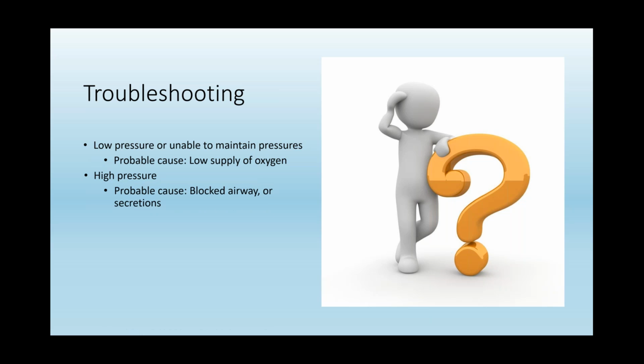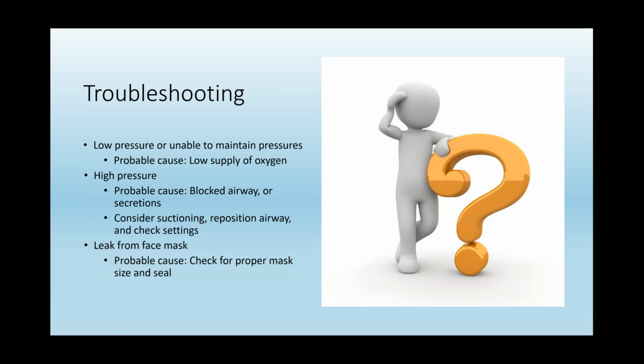If you have a high pressure, one of the probable causes is that the patient has a mass amount of secretions, or their airway is blocked for whatever reason. So you could try suctioning them or repositioning them. Like I said, in theory they're supposed to be sitting pretty high up in a seated position, so maybe reposition them. Check that the settings and the oxygen flow are appropriate. And then the leak issue, which I keep mentioning, seems to be the most common one for me at least: there's a leak in that mask. So check that you have a proper seal. Or maybe you're using a mask that's too small or too big, and you need to switch out masks.